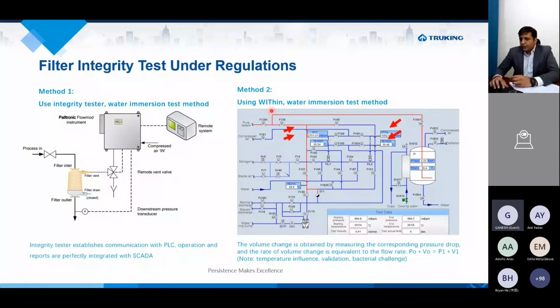The volume change is like, in high school we have learned a formula, P naught V naught is equal to P1 V1. That is the basic governing formula of this WIT test. So the volume change is obtained by measuring the corresponding pressure drop, basically. And the rate of volume change is equivalent to the flow rate. So volume change, flow rate. If there is a deviation, there is an issue in the integrity of the filter.